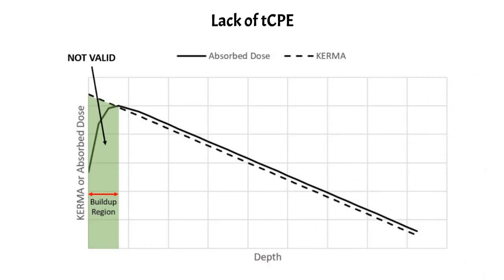Another limitation is the lack of transient charged particle equilibrium, or TCPE. As shown in the PDD formalism, there is a buildup region at the surface which is a region of non-equilibrium — there is no simple relationship between the kerma and absorbed dose in this buildup region. Beyond the depth of D-max where TCPE is established, that simple relationship exists, but the hand calculation formalism is not valid in the buildup region because it is very hard to quantify and predict, being highly dependent on the detector used, its volume, energy response, and other factors.